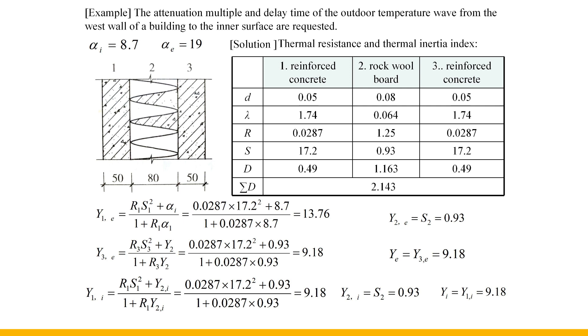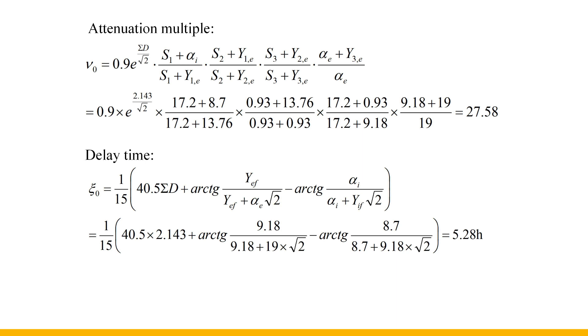Then, Y1E and Y3E are calculated according to the temperature wave from outside to inside. Y2E equals S2 because D2 is greater than 1. YE in the delay time calculation formula is Y3E on the surface facing the wave. Y1I is calculated according to the temperature wave from inside to outside; YI in that formula is Y1I on the surface facing the wave. Y2E does not need to be recalculated since D2 is greater than 1 and equals S2. Y3E belongs to layers after D exceeds 1 so it is not required for the indoor wave calculation.